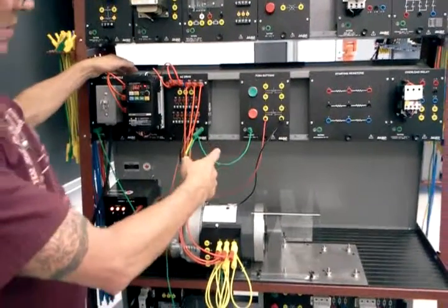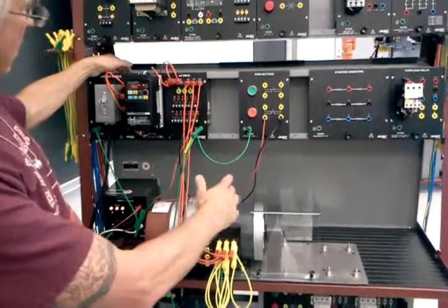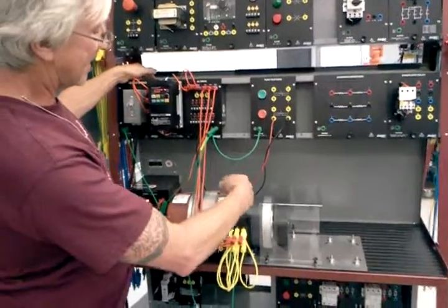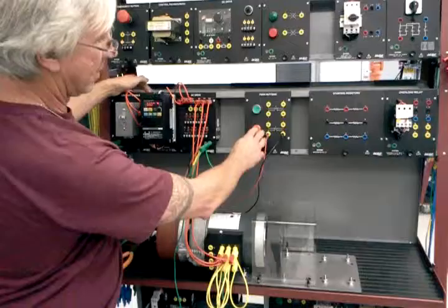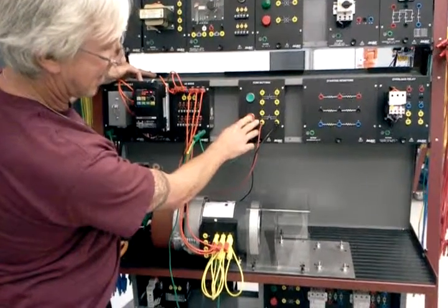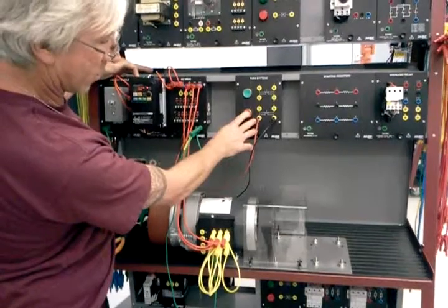And when I push the stop button, it's going to cut off the AC current to the motor and then it's going to induce DC current to stop the motor. If I hold the button, the current is consistently going in and the motor is going to stop rather quickly.